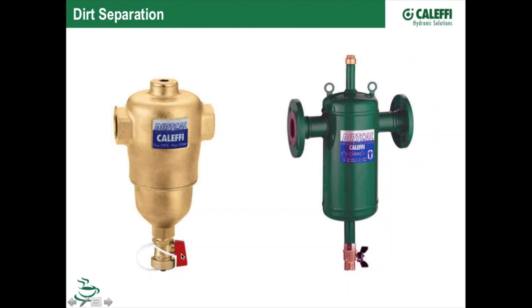We're driving that out. It's going to go to the bottom of this, and now we come back, put a bucket or something onto this, open the valve, and we can flush it out. I like to see what comes out of it so you know what's in your system. You might learn some things about what you have to do for treatment of that system. If you see a lot of rust and scale come out of this thing, oh gosh, I better get back and do a better power purge on this system.